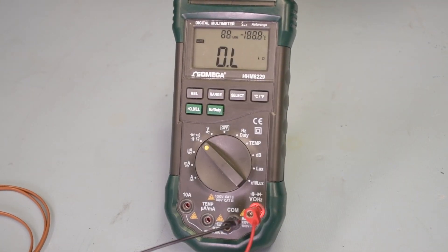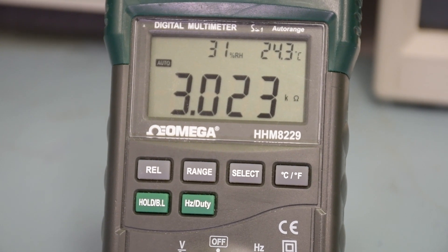So, I'm going to take my ohm meter here, and we're checking for resistance, 3.023 kilo ohms. I think we have a thermistor here, because an RTD doesn't have a resistance nearly this high.